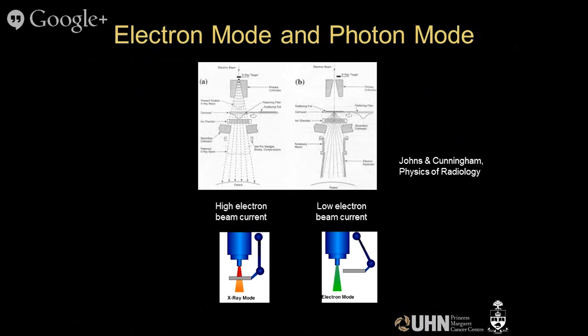As we learned this week, there are two modes of operation. There's a photon mode where you have an electron beam striking a target. The target then goes through an upper collimator, flattening filter, jaws, and so on, and makes a therapeutic beam. You can also have a mode where you have an electron beam and the target is removed. You still go through the upper collimator, then you use scattering foils, the dose chamber, and a collimation system. And as we learned when we talked about the powers, the amount of beam current that you need to generate a photon beam is much higher than you need in electron mode. So the whole safety of the system depends on this target being in place, to make sure that high power is being absorbed by the target and not too much of it is going into the electron beam.